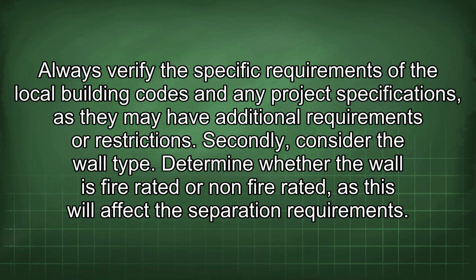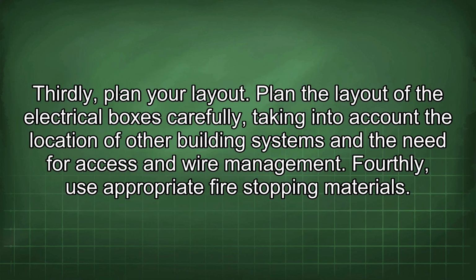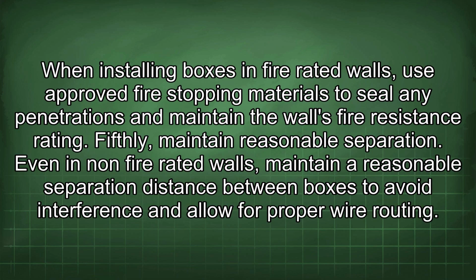Secondly, consider the wall type. Determine whether the wall is fire-rated or non-fire-rated, as this will affect the separation requirements. Thirdly, plan your layout. Plan the layout of the electrical boxes carefully, taking into account the location of other building systems and the need for access and wire management. Fourthly, use appropriate fire-stopping materials. When installing boxes in fire-rated walls, use approved fire-stopping materials to seal any penetrations and maintain the wall's fire resistance rating. Fifthly, maintain reasonable separation.